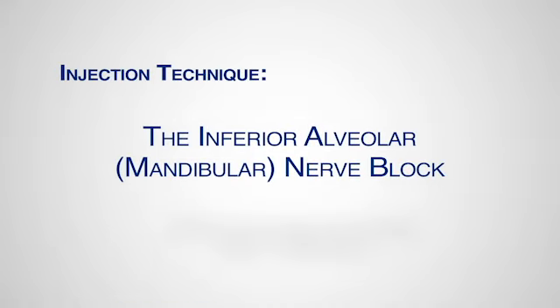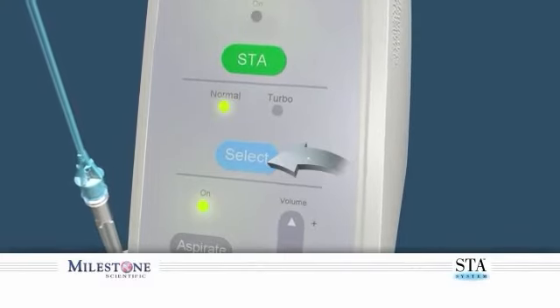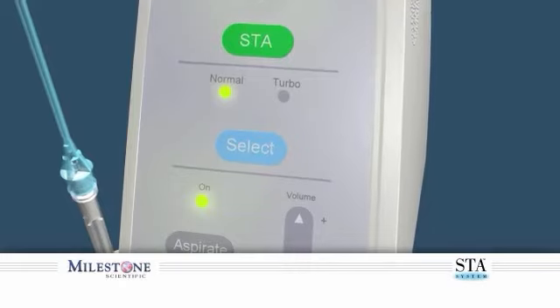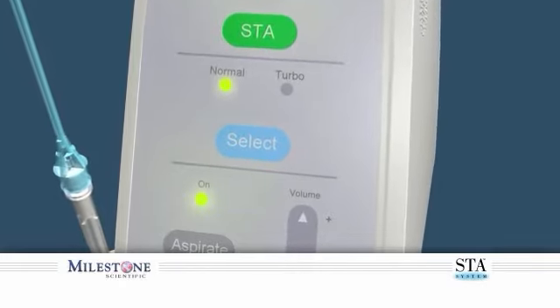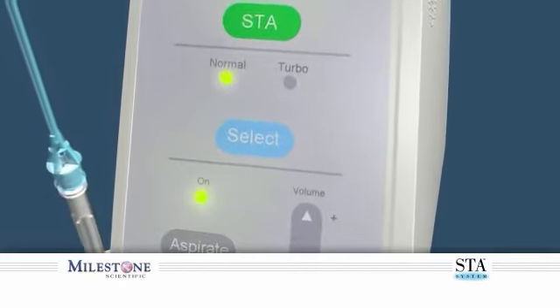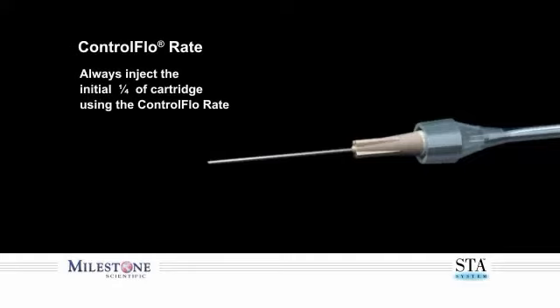Injection Technique: The Inferior Alveolar Mandibular Nerve Block. Set the wand system to the normal mode, which allows the system to function with two distinct flow rates: the controlled flow rate and the rapid flow rate. Utilize the controlled flow rate to administer a minimum of one quarter of the cartridge for the initial phase of the block injection. Once the patient feels the onset of soft tissue anesthesia, transition to the rapid flow rate.